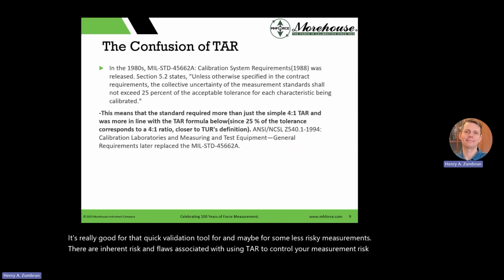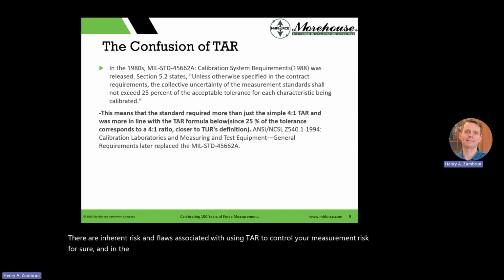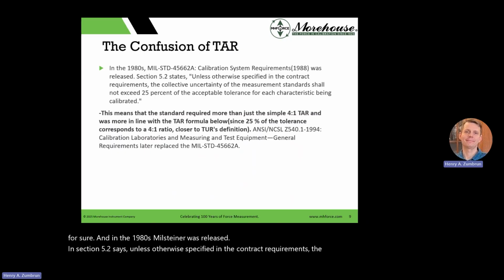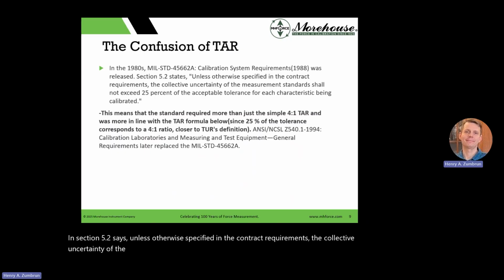In the 1980s, MIL standard was released. And section 5.2 says, unless otherwise specified in the contract requirements, the collective uncertainty of the measurement standard shall not exceed 25% of the acceptable tolerance for each characteristic being calibrated. So what this really means is that the standard required more than just a simple 4 to 1 TAR rule that many people use. They just say, hey, I have the accuracy of the equipment, the accuracy of my standard, I'm going to do that.